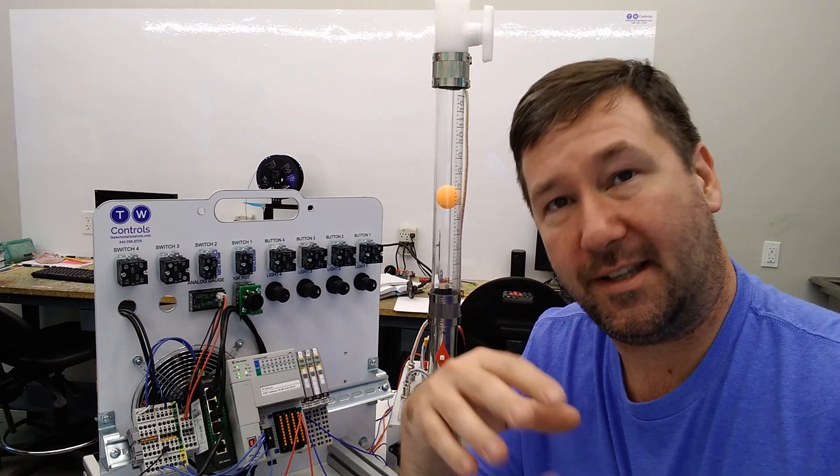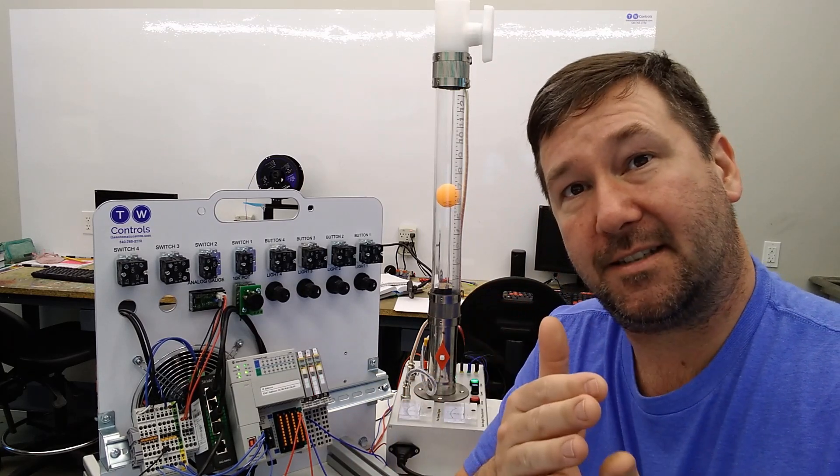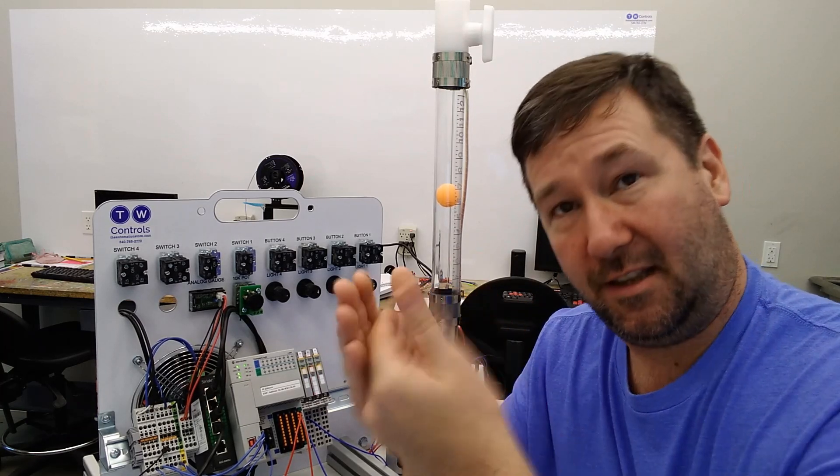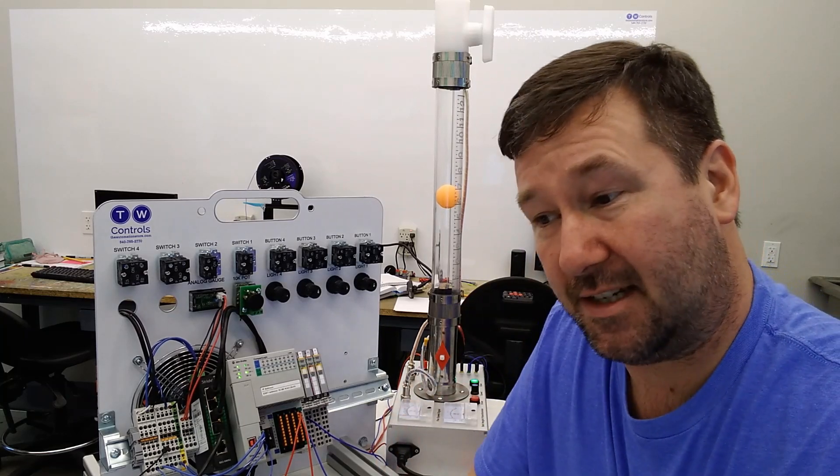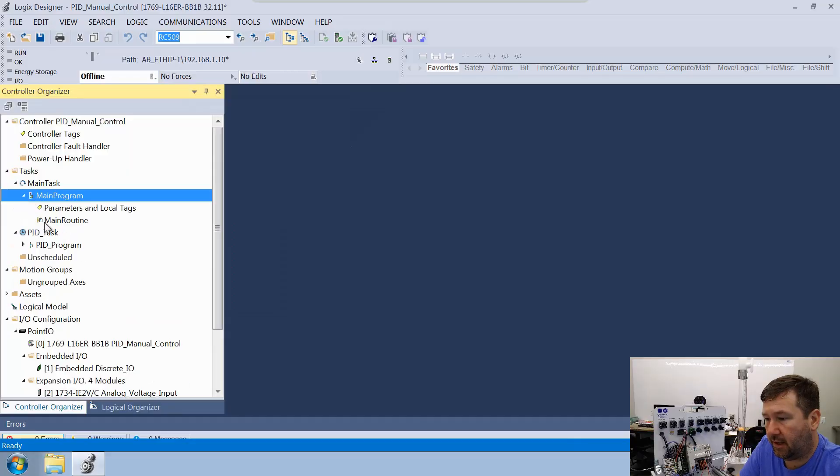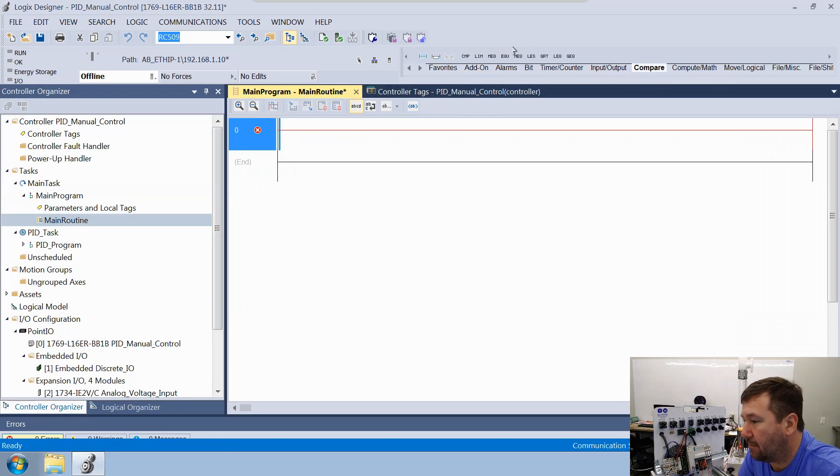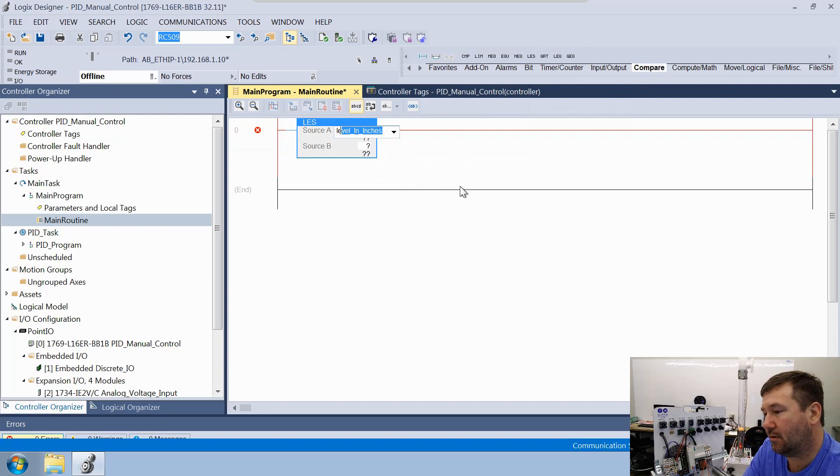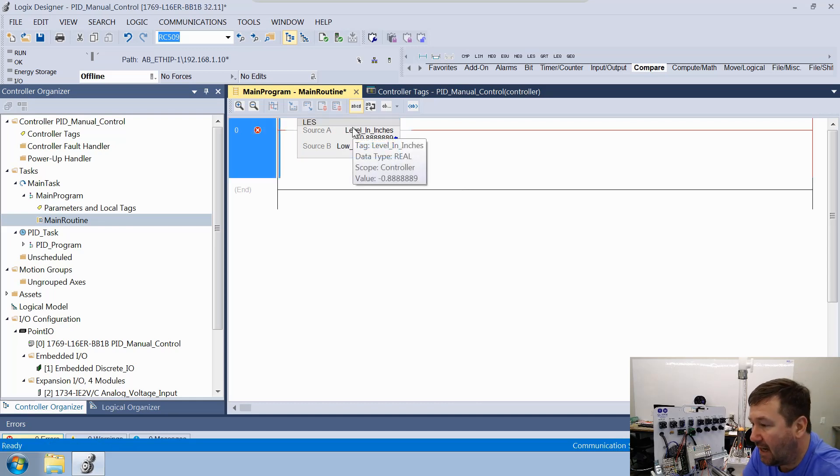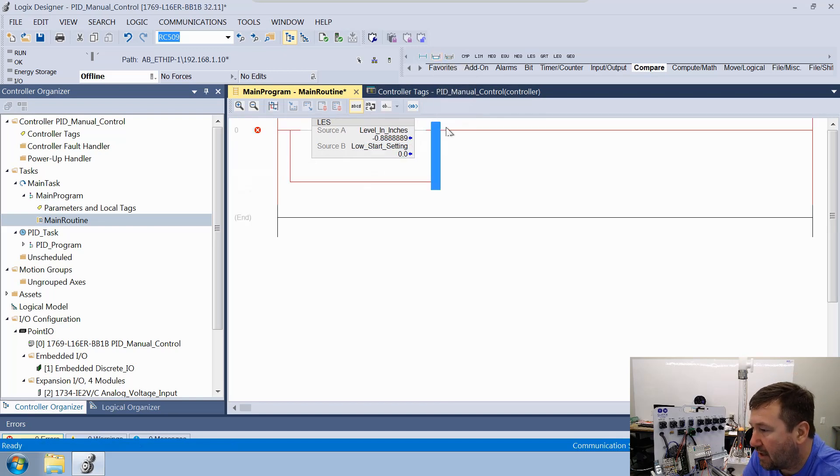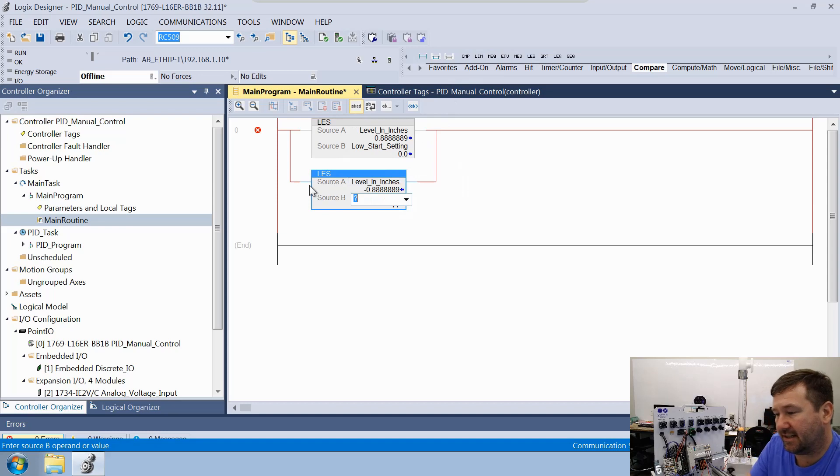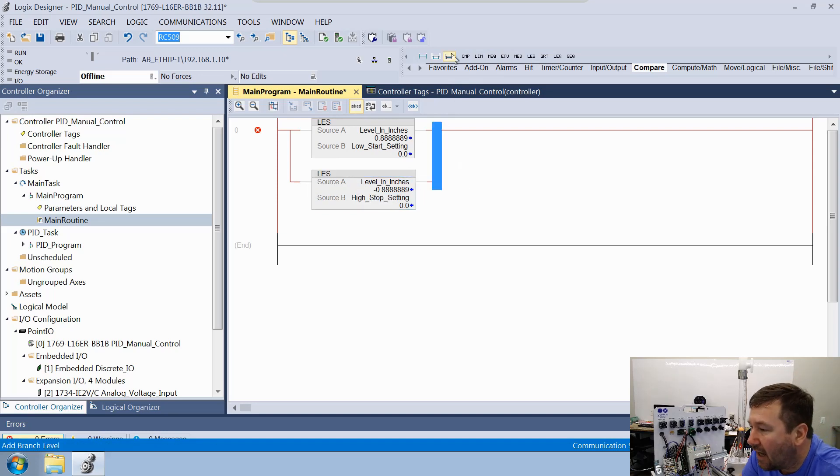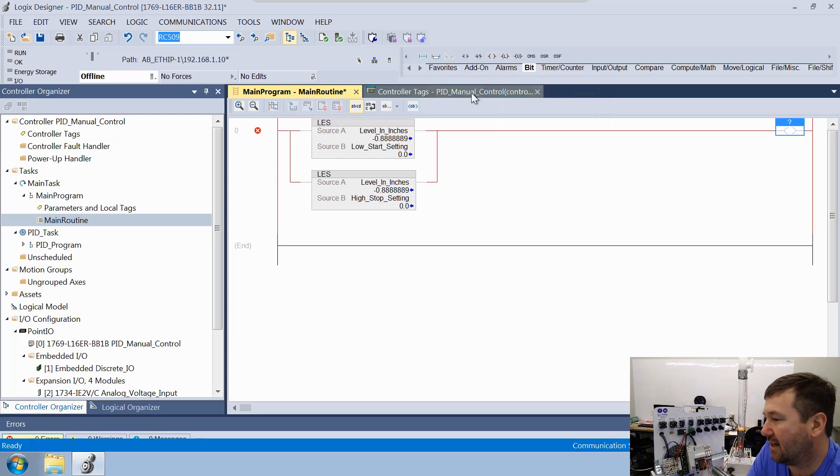We're not actually going to do this within our function block programming, because the on-off control is probably something you see more in ladder. Also, I want to begin easing some people into the idea that everything doesn't have to be 100% ladder or 100% function block or 100% structured text. So we are going to go up to our main task and let's open up our main program and then our main routine. Let's go over to our compare tab and let's bring down a LES less than instruction. We're going to look at that level in inches. Our source B is going to be that low start setting.